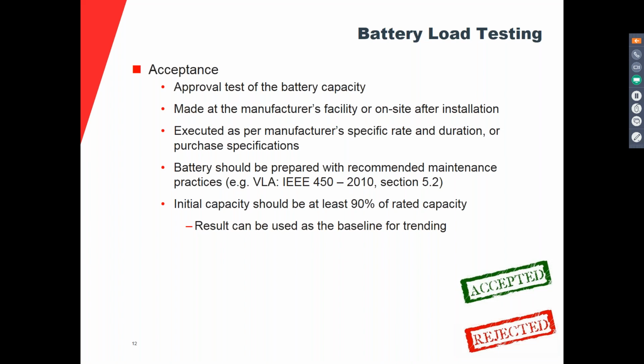The battery should be prepared and inspected with other recommendations that are in the standard. As the result of the test, the battery should be at least 90% of the rated capacity. And this could be because the capacity of the battery is still developing and has not totally formed. So this value is accepted, but it should be at least 90%, and should not be below that. And of course, it can be higher than 100%. As a matter of fact, it usually will be higher than 100%. And whatever result is obtained can be used as the baseline for the trending.